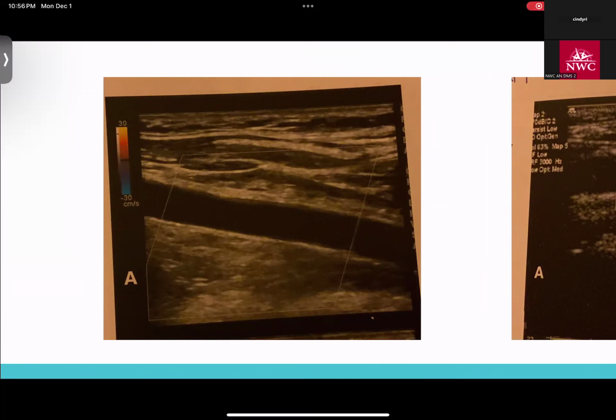So, although all of those would be correct, what's the first thing that you noticed as being the thing that caught your eye as being very wrong? It's the steer of your color box. So, the steer of your color box is, if you can't see it, the steer is not parallel with the direction of flow.